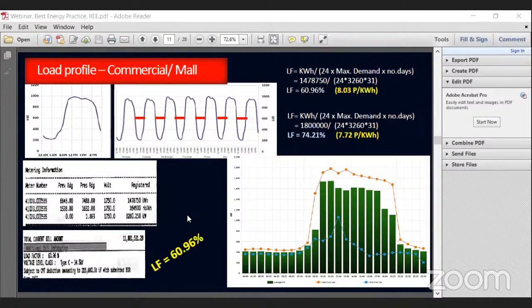Balik tayo sa load factor profile. Yung hinighlight ko ng red, pag meron kang BPO o may load ka sa gabi, tataas yung energy mo at the same demand. Kaya ang load factor mo, pag kinompute mo ngayon using the formula, ay 74.21%. Ang magiging effective rate mo, pag sinimulate mo yan, is 7.72 pesos per kilowatt hour. May kinalaman ang load factor sa effective rate. May mga buildings kami na magandang load factor, mas maganda yung rate, mas mababa.